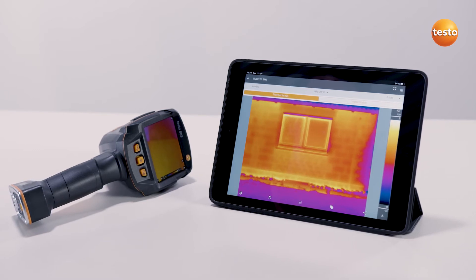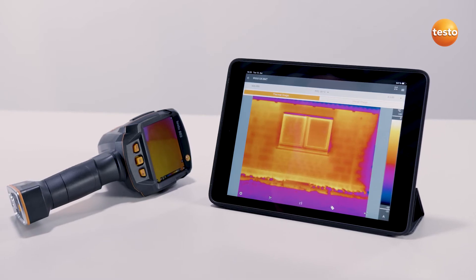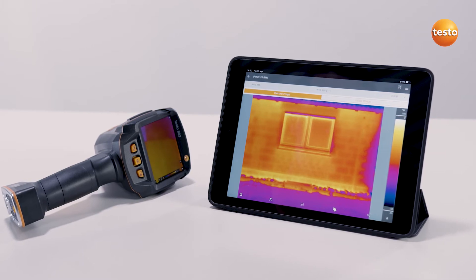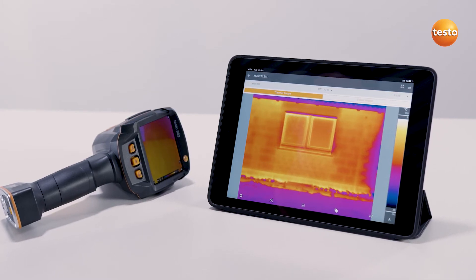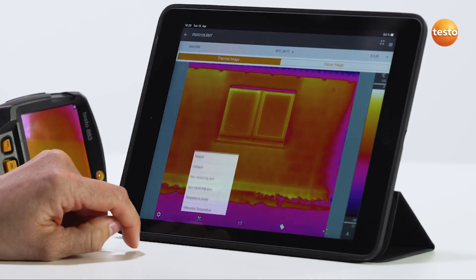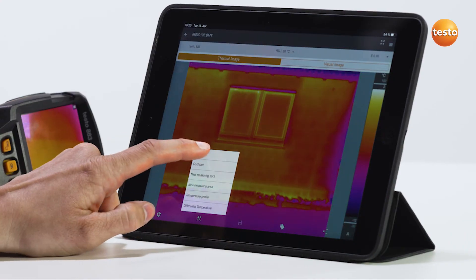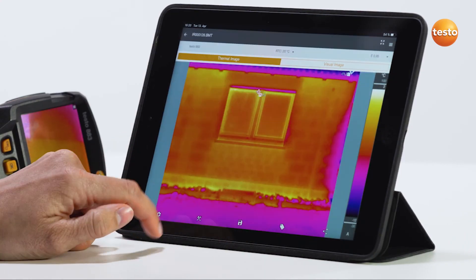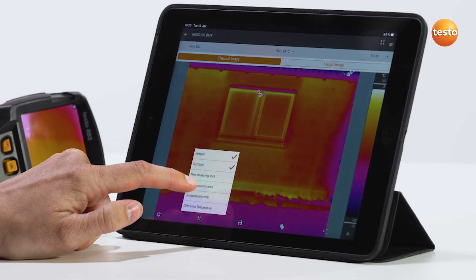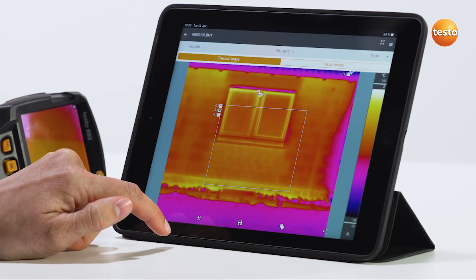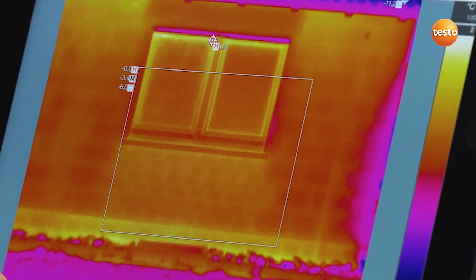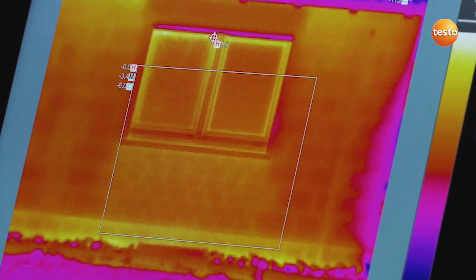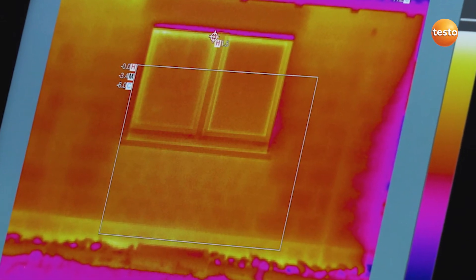Now to the measurement functions of the app — and there are many. Simply tap on the measurement function button and select the desired tools. For example, you can have hot and cold spots displayed to you. You can also set new measuring spots or carry out an area measurement in which minimum, maximum and mean temperatures of the area are displayed automatically.